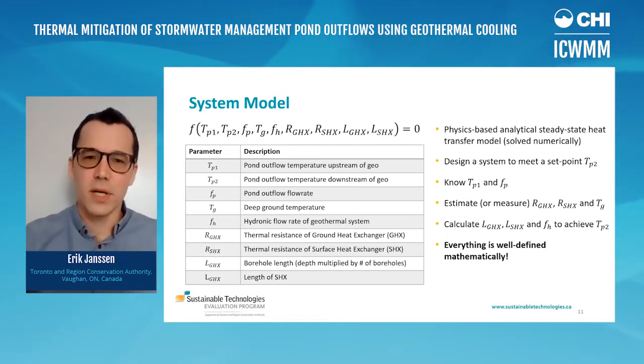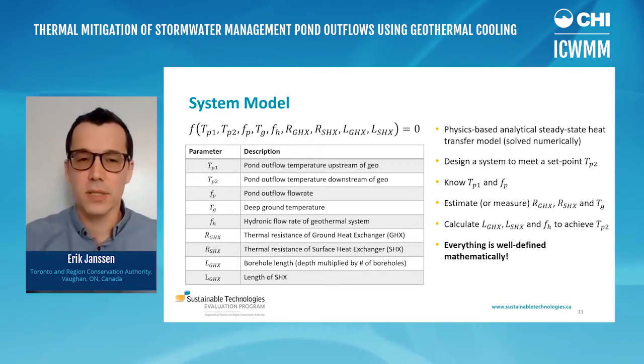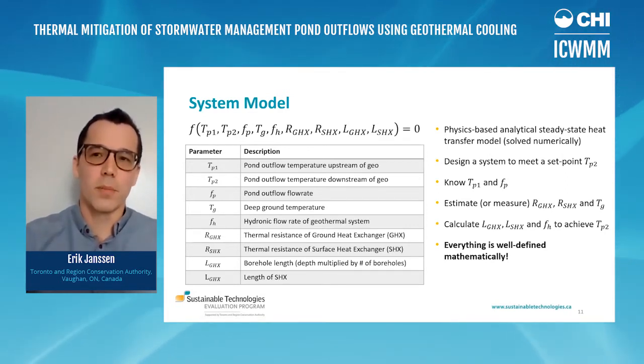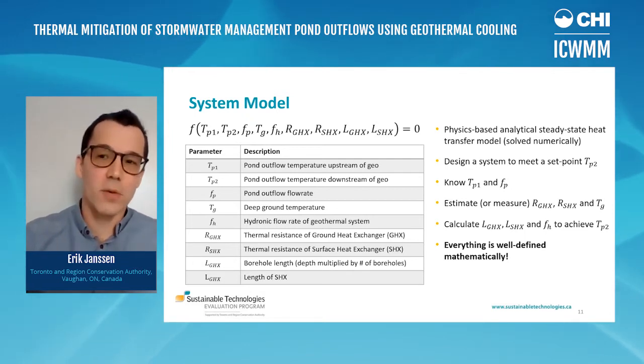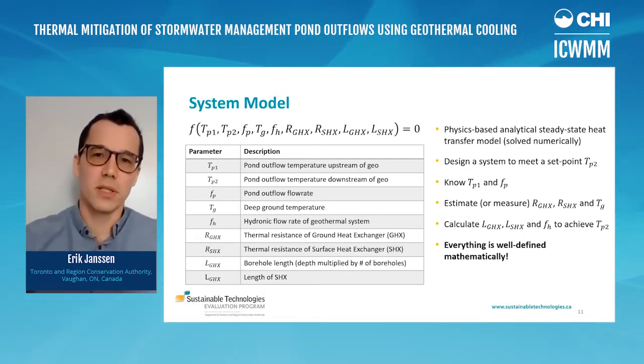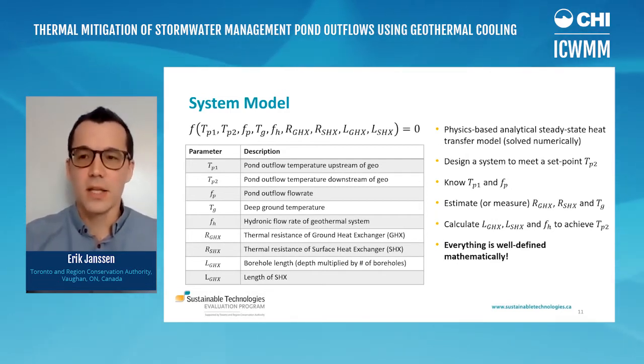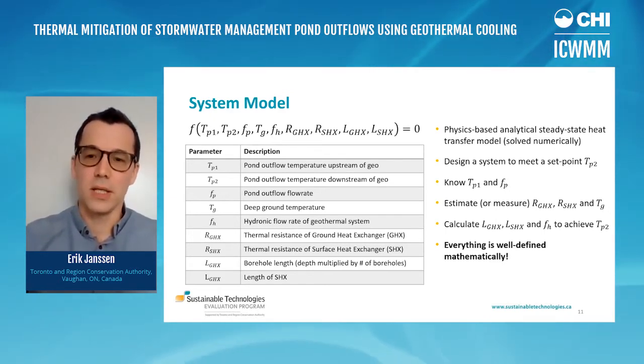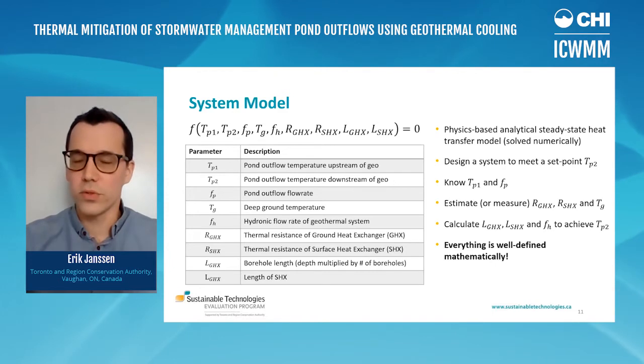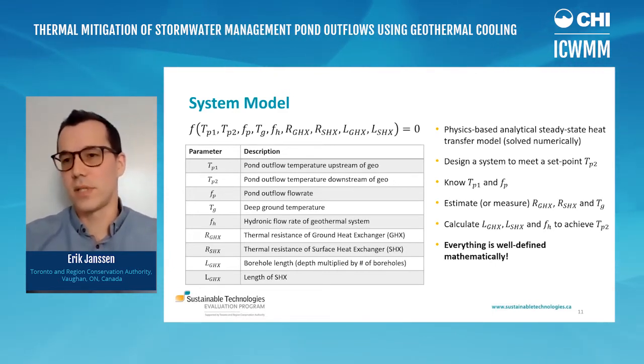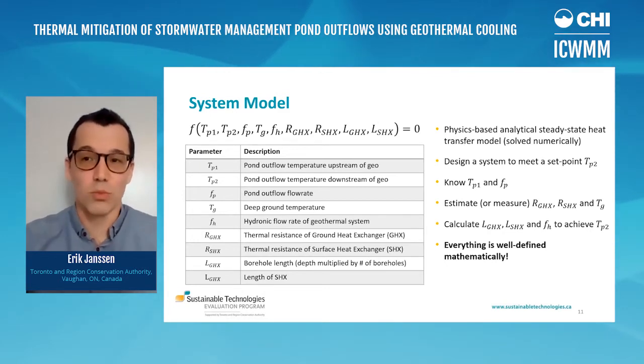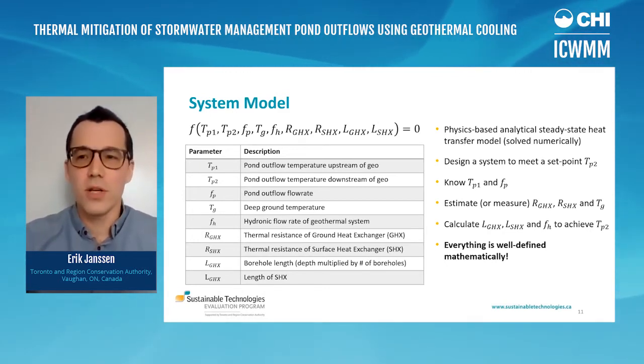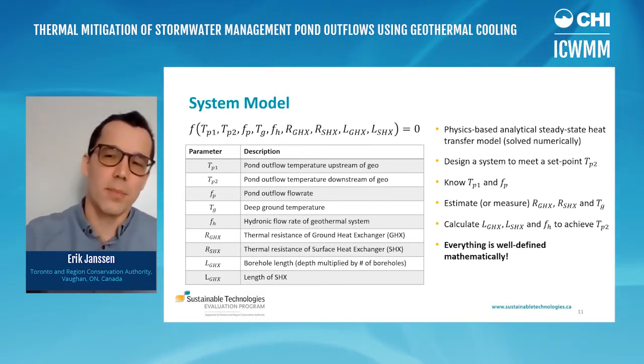If we're going to do a design procedure, we would take for example, a set point temperature that we want to meet. Let's call it TP2, might be 24 Celsius. We would know the temperatures coming from the pond and the pond flow rates as well. Then we can estimate or measure some of the other parameters. For example, the thermal resistance of the ground heat exchanger and the surface water heat exchanger. These are just numbers that we would know from other geothermal installations. We'd estimate a deep ground temperature as well, TG. And then we could do a cost optimization calculation to size the lowest cost number of boreholes and also length of piping required to achieve our set point temperature. So the good news is that this is all well-defined mathematically. I'm not going to show any equations more than this, but it's all laid out in the paper that's accompanying this presentation.